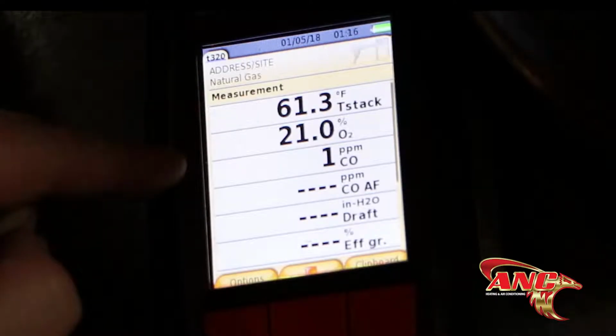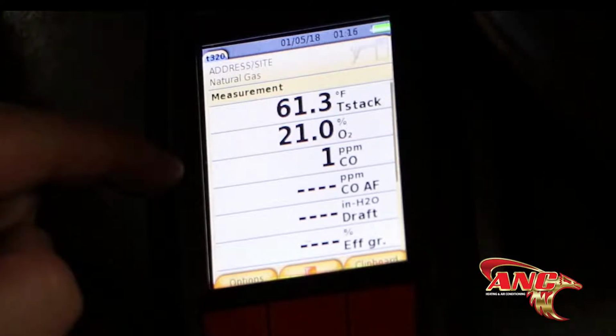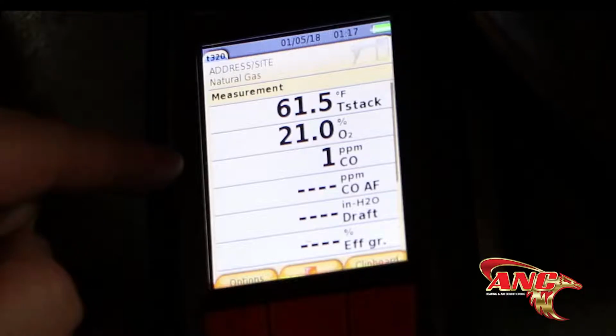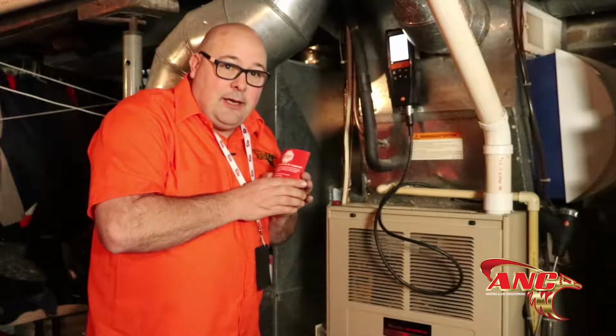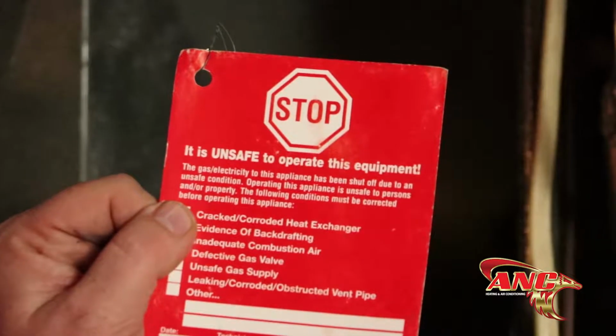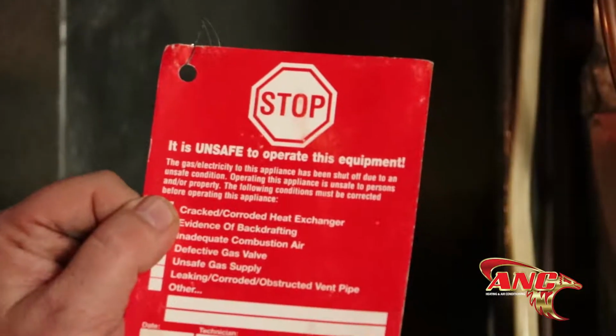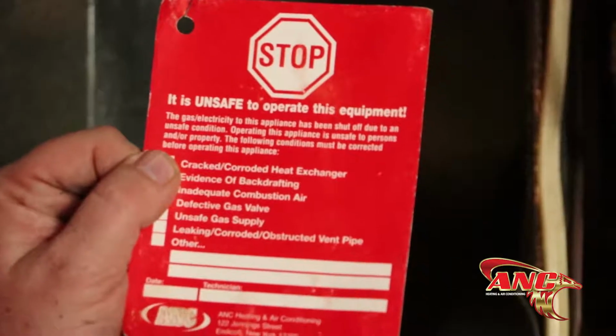Not a huge concern. If it starts getting up toward 200, we know there's a major problem and probably a heat exchanger issue, and all manufacturers will tell you at 200 that is most likely the problem. The big number we don't want to see is 400. So at 400 parts per million in the flue, you get one of these. And this is something we don't want to give out. It's something you do not want to get. But it is deemed a dangerous appliance by the American Gas Association and NYSEG.